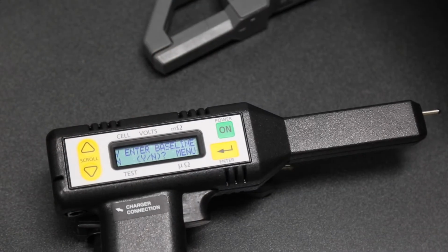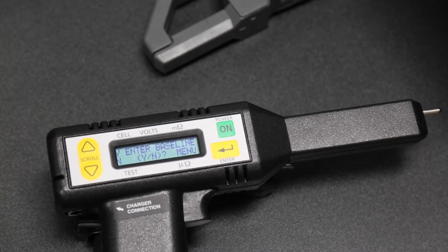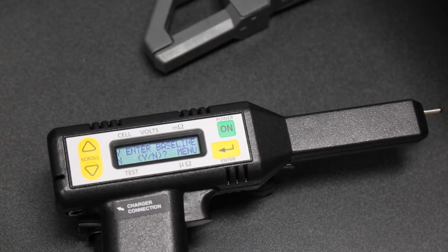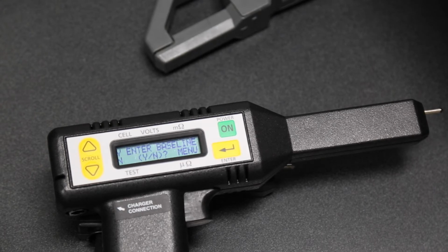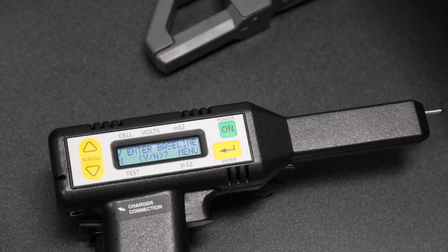Now we can enter a reference baseline value and alarms if we choose. The BITE2 will then indicate which cells pass and which fail. The other option is we can transfer the data to our PowerDB software. This software will automatically calculate the baseline value for each string and analyze the data. So for the purpose of this test, I will select No.